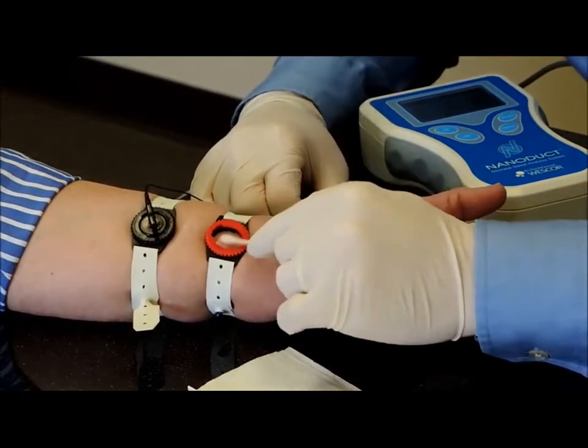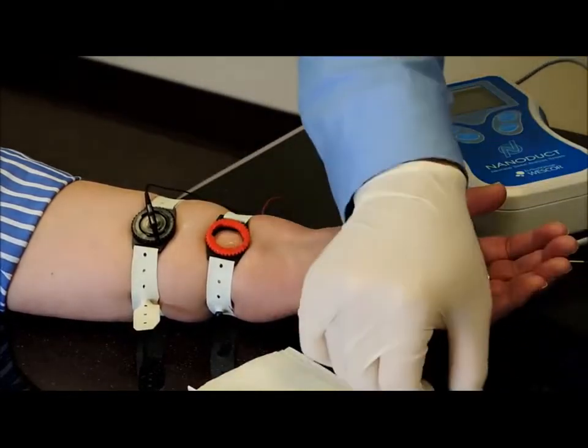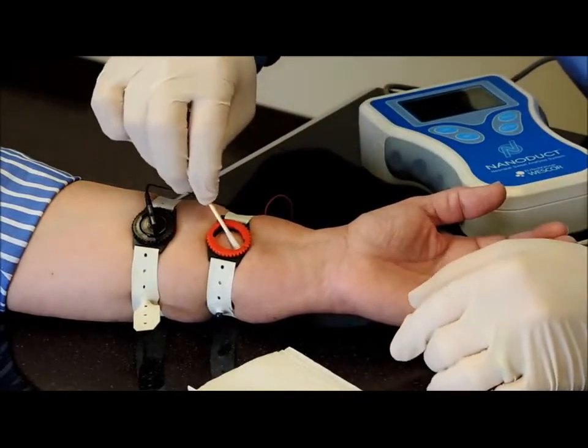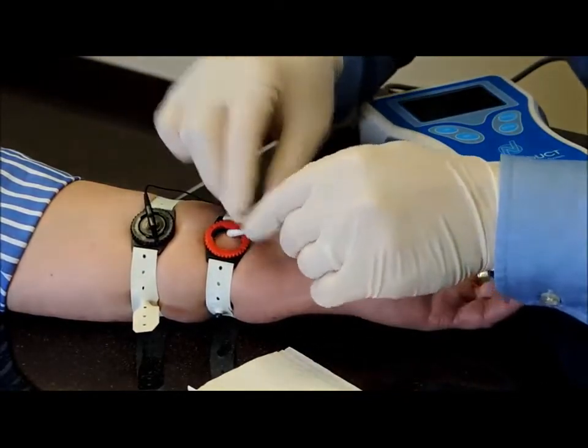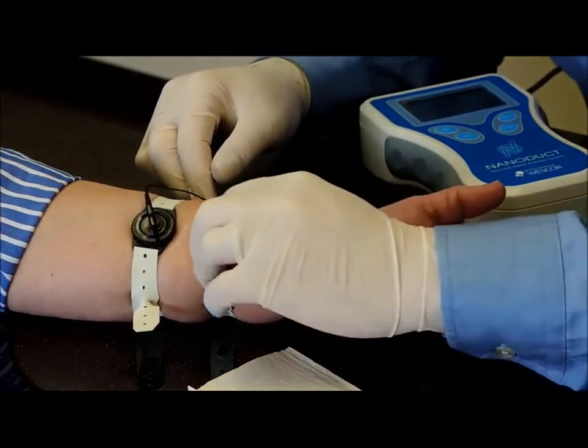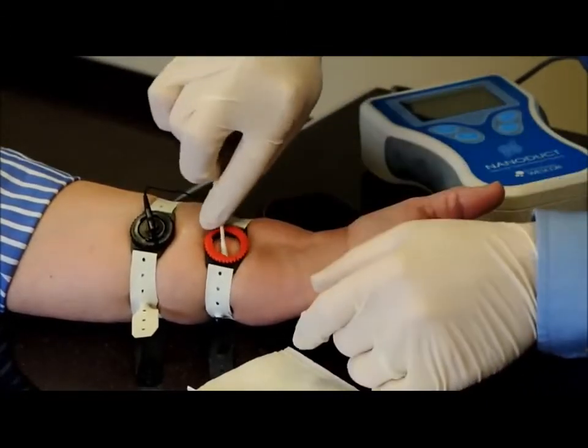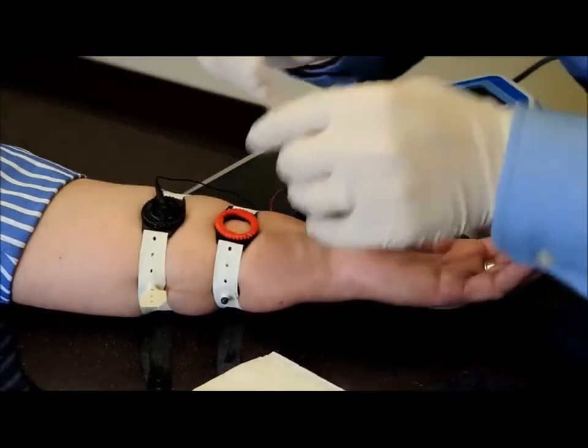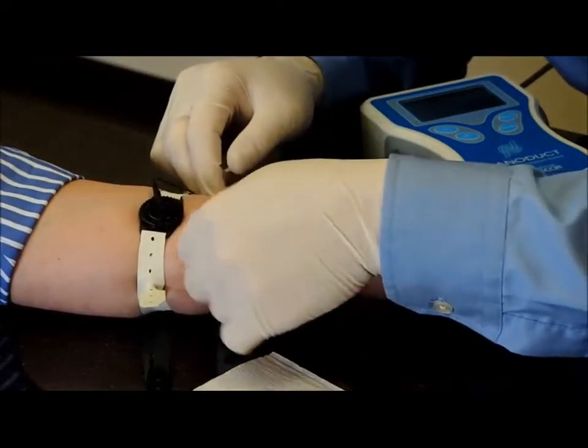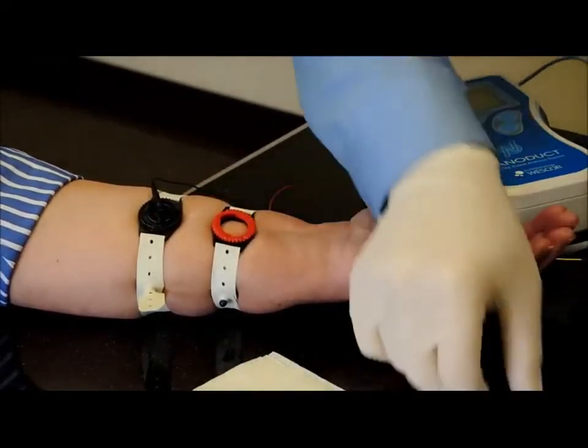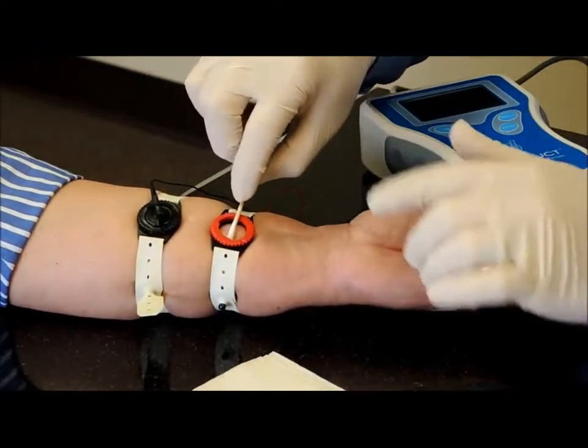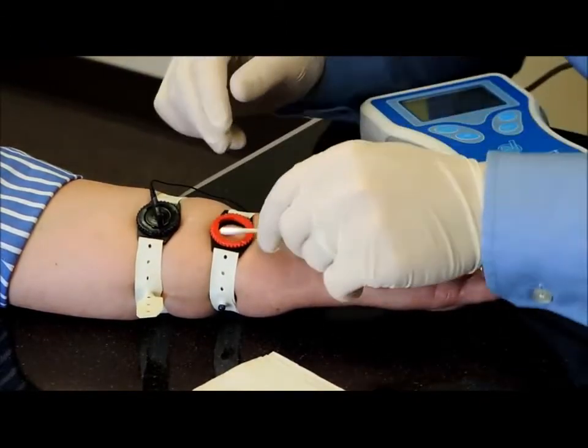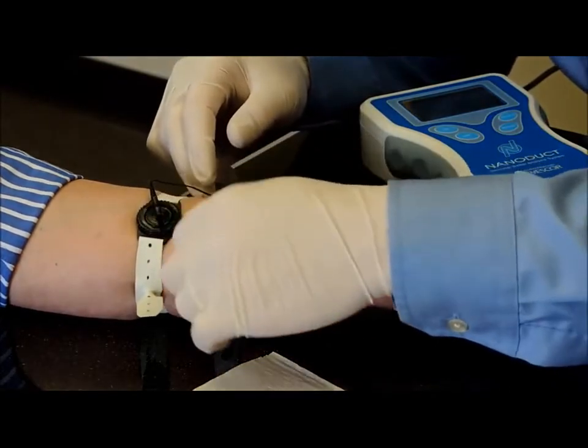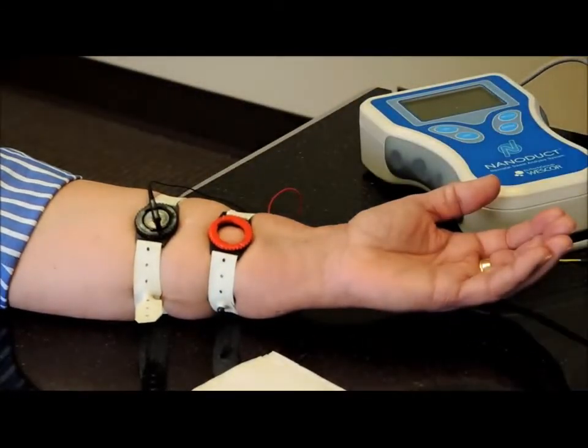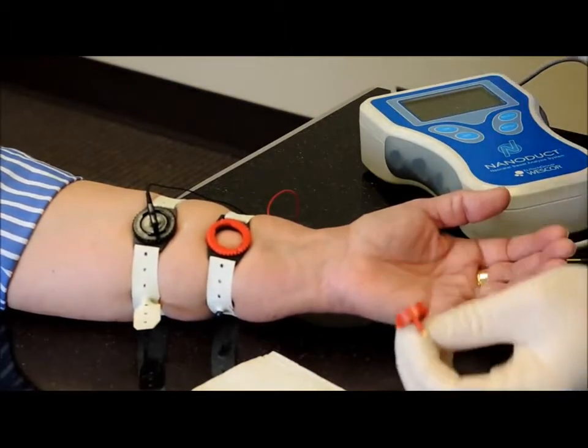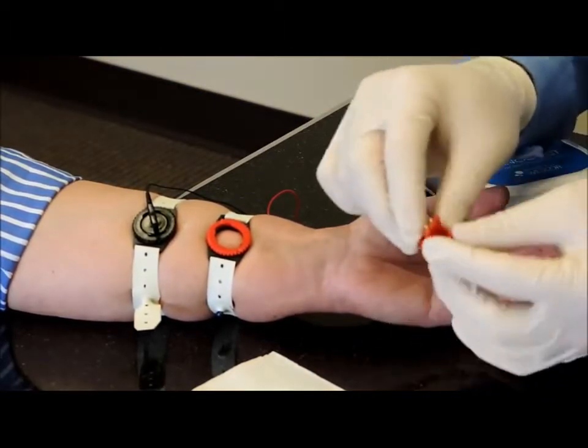Now, one thing that's really important is to use a few of these swabs and make sure you dry that really well after it's been wet, and get underneath the holder all the way around, because some of that liquid can go underneath that holder. You want to just make sure that's really dry. You can see when it's dry. The cotton absorbs the liquid really well. So we're back dry as we should be. So at this point we're ready to apply the sensor cell.